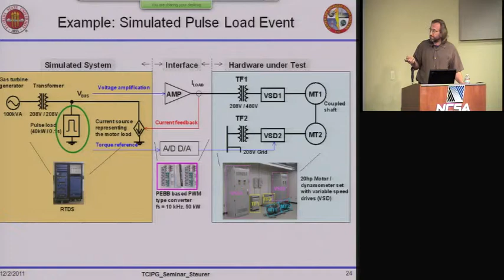The variable speed drive draws more or less sinusoidal currents from the grid because it's an active front end. Then there's an onset of the pulse load, which drastically reduces the frequency within about 100 milliseconds. The frequency drops because it's a gas turbine generator - you put a load on it and it drops in frequency. Everything's fine, and the frequency picks back up when you release the pulse load.